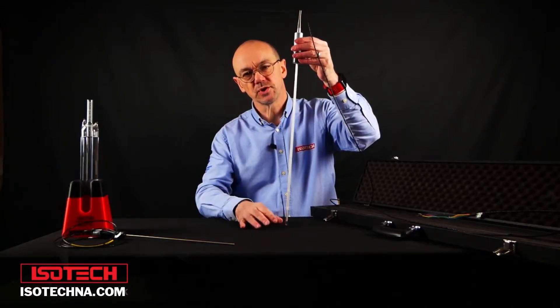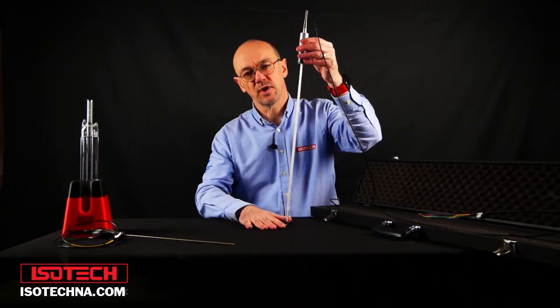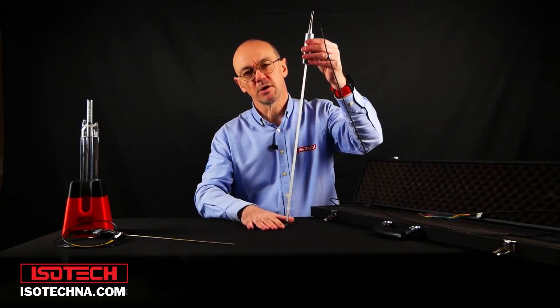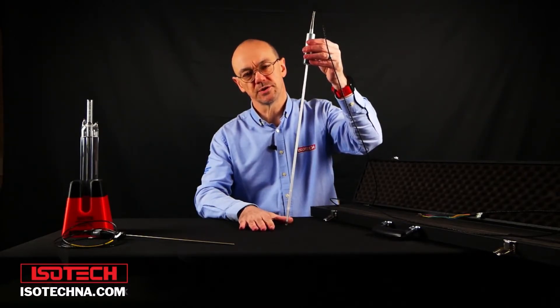You can use metal-sheathed SPRTs, but inside the construction is just as fragile as the quartz glass ones. And with a metal-sheathed SPRT, more heat will flow along the stem, giving a larger immersion error compared to a quartz SPRT. We always recommend quartz SPRTs at Isotech.